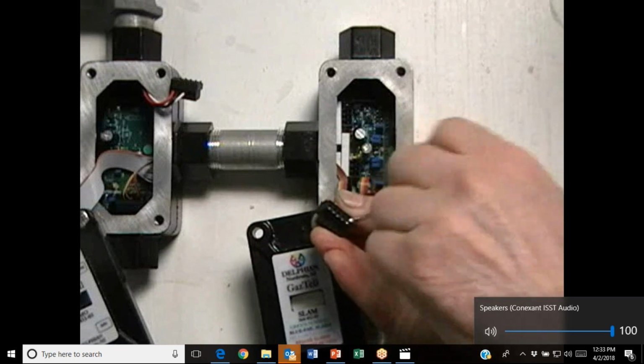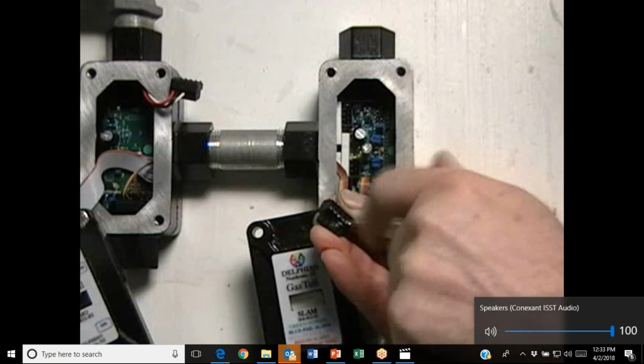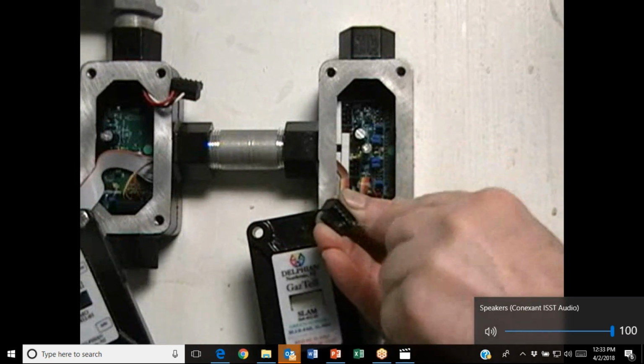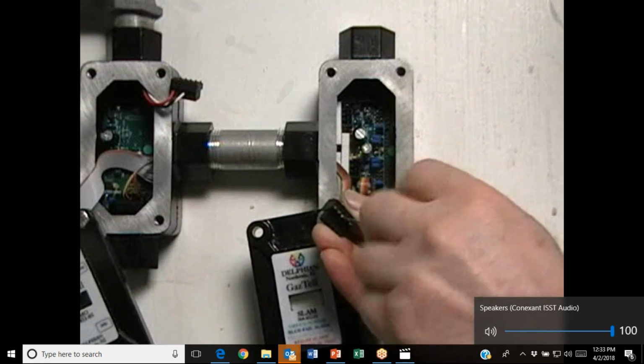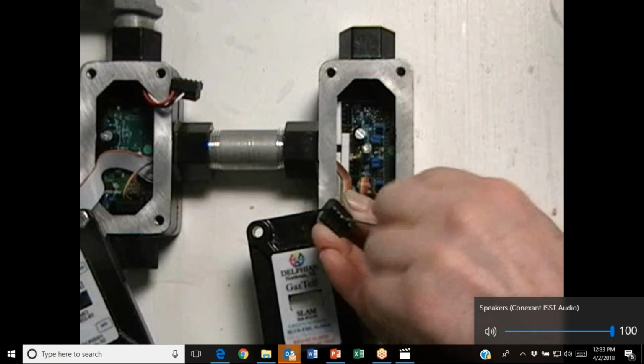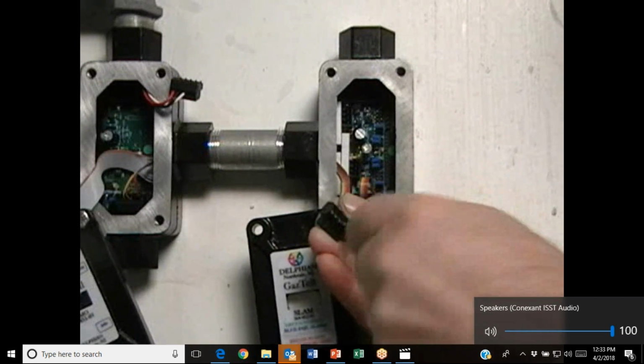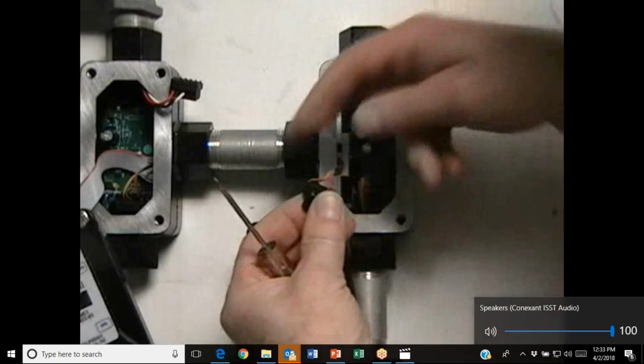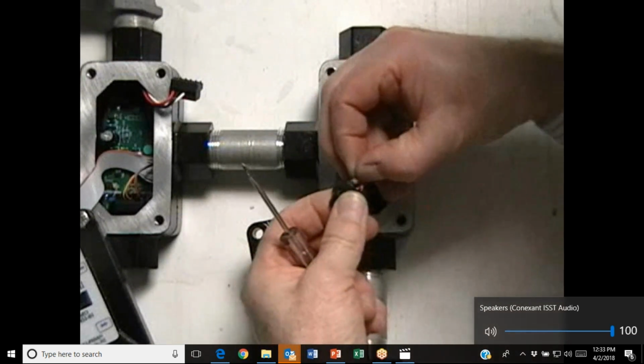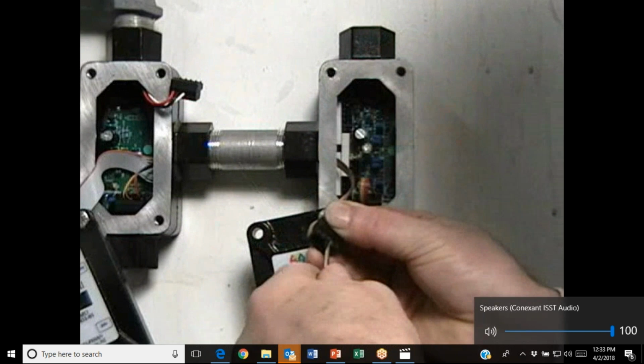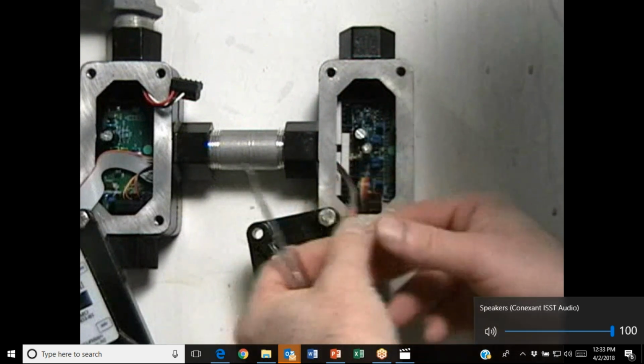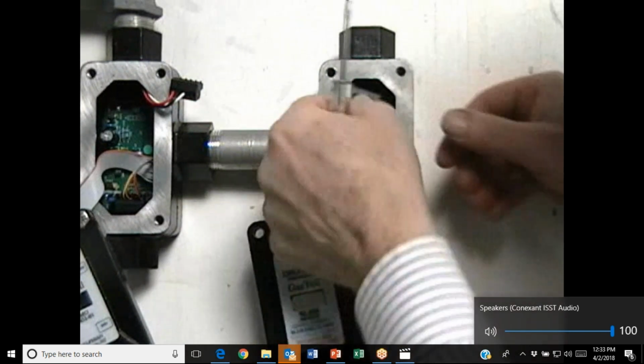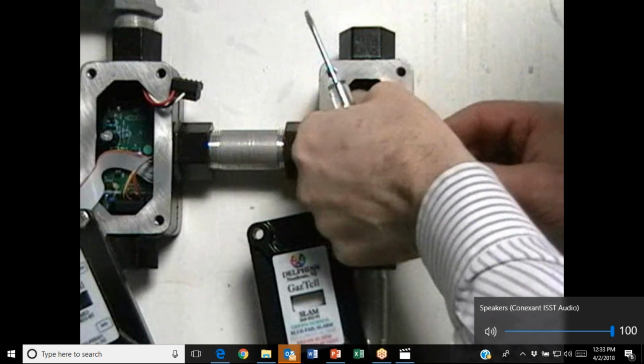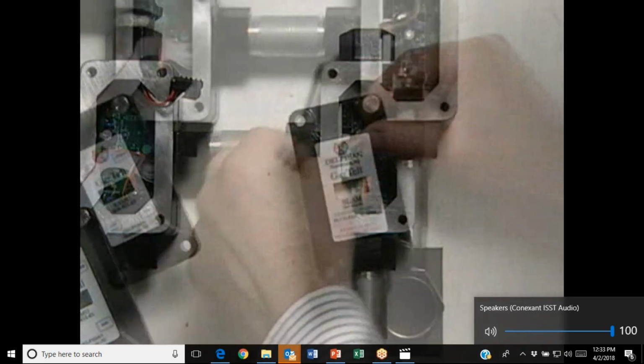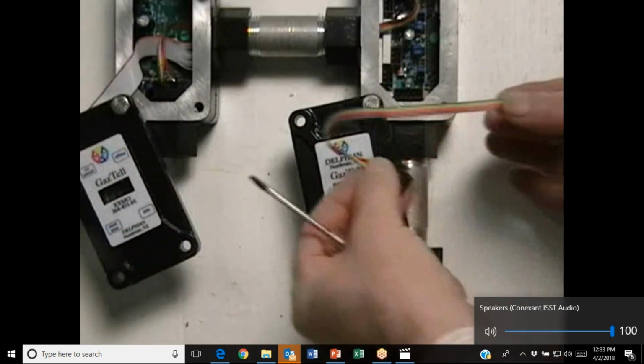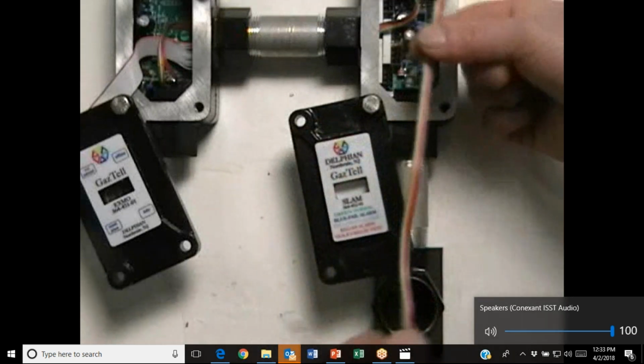Once the cables have been pulled through the conduit, terminate the wires with the 5-pin terminal block supplied. Make sure the wires are secure by giving them a light tug. Then plug them into the 5-pin socket inside the housing. The five conductor cable is to transmit the 4 to 20 mA signal and the RS-485 communication between the detector and the accessory module. The remaining two wires will supply the plus and minus DC power.